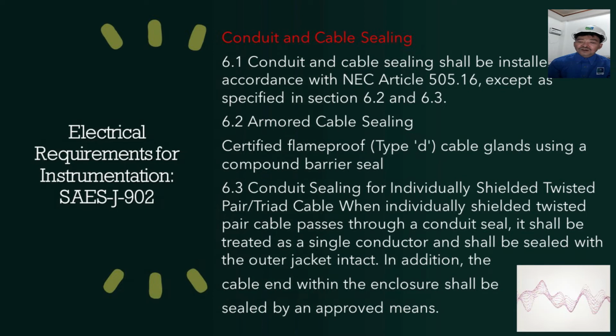Conduit and cable sealing shall be installed in accordance with National Electrical Code, Article 505, except as specified in Sections 6.2 and 6.3. For the armored cable sealing, use a certified Type D cable gland using a compound barrier seal. Conduit sealing for individually shielded twisted pair cable: when individually shielded twisted pair cable passes through a conduit seal, it should be treated as a single conductor and shall be sealed with the outer jacket intact. In addition, the cable end within the enclosure shall be sealed by an approved means. So this requires a method statement or procedure, because this is a special process in electrical installation.